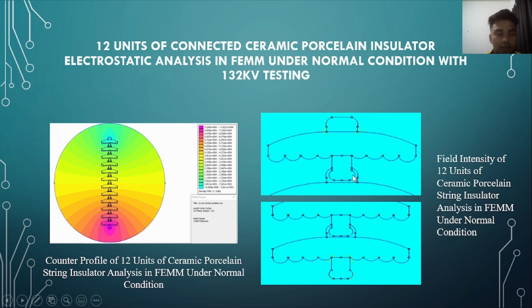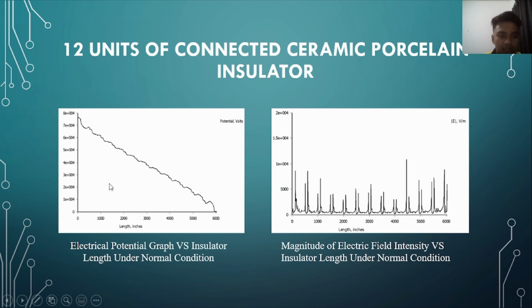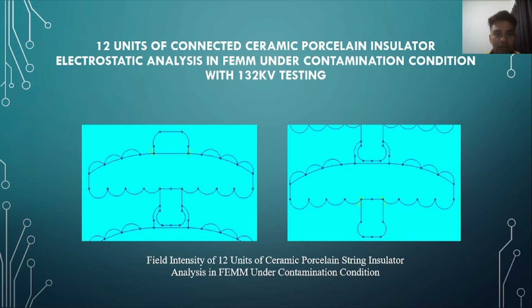Next, we continue to the 12 unit ceramic insulator string in FEMM under normal condition, which is 132 kV per phase. What we can see is the circle for the first unit and the field intensity of the first unit. Here you can see the field intensity under the cap and under the pin. Next is the result for the first unit: the electrical potential graph along the insulator under normal condition, where you can see the graph decrease, and the graph for the magnitude of electric field intensity versus insulator length under normal condition.